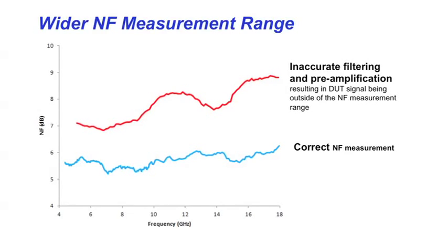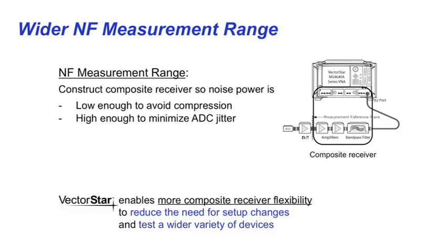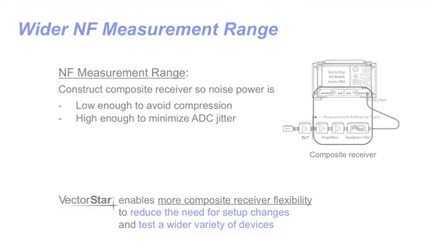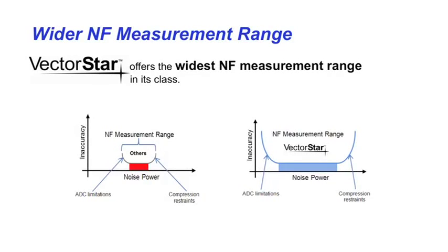If too little amplification is applied to the composite receiver, there may be too much jitter from the instrument's A to D converter. If too much amplification is applied, resultant power levels can cause compression and impact the measurements. Selecting a VNA that provides a wide noise figure measurement range enables greater composite receiver configuration flexibility, simplifying setup and offering the ability to test a wider variety of devices. The Anritsu VectorStar family offers the widest noise figure measurement range in its class.